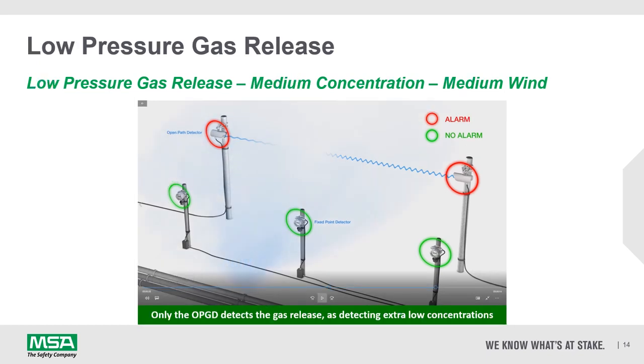Here we have a different scenario, a low pressure gas release. By the time the gas has reached the point detector, it has diffused and diluted to a level that is not detectable by the point detector. However, on an open path detector, which effectively counts the number of molecules in the beam, it can be detected. So an open path gas detector is ideal for a large, low concentration gas release.